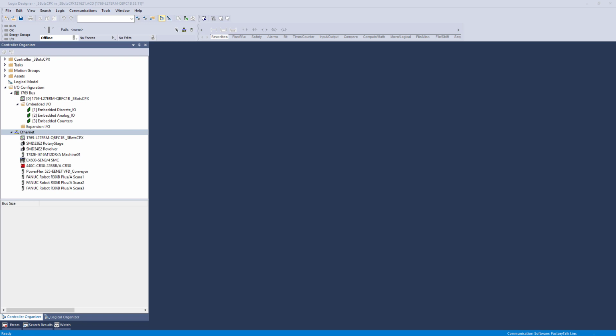And then we need to add the EX600, which is an SMC valve body. In other words, it has a manifold with solenoid valves on it, and it also has input modules, output modules, and an Ethernet interface. That has to be added, and that was probably the most complex of all the Ethernet devices, getting that set up properly and added.